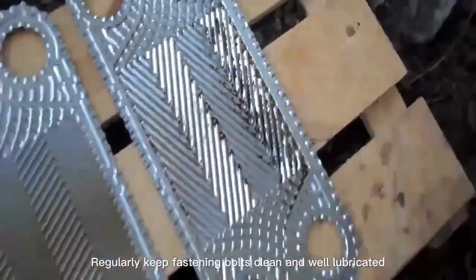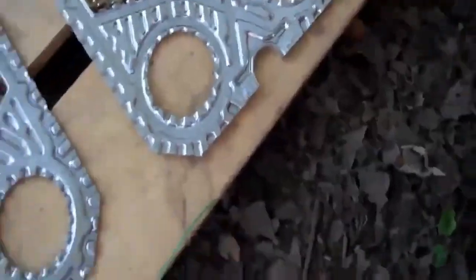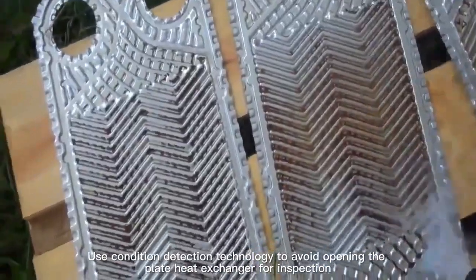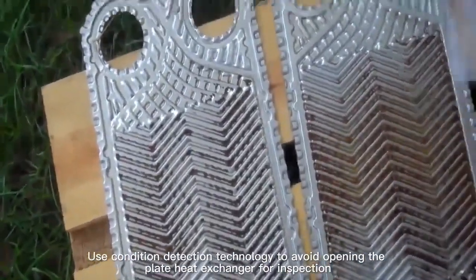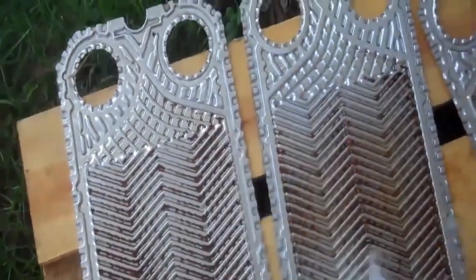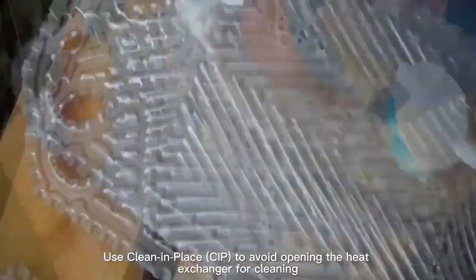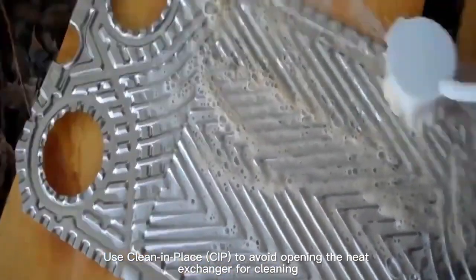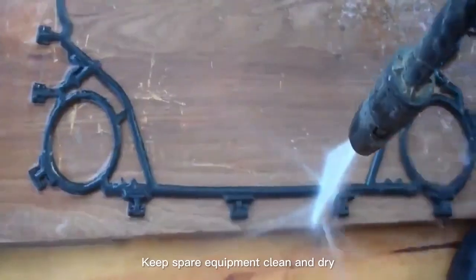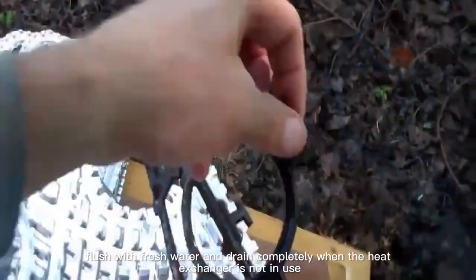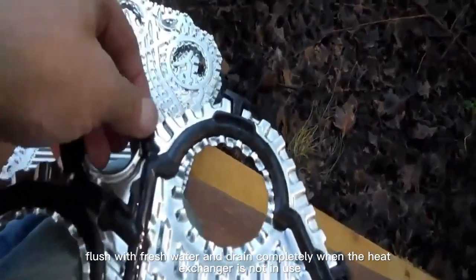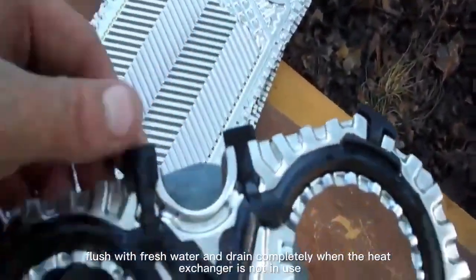Regularly keep fastening bolts clean and well lubricated. Use condition detection technology to avoid opening the plate heat exchanger for inspection. Use clean in place (CIP) to avoid opening the heat exchanger for cleaning. Keep spare equipment clean and dry. Flush with fresh water and drain completely when the heat exchanger is not in use.